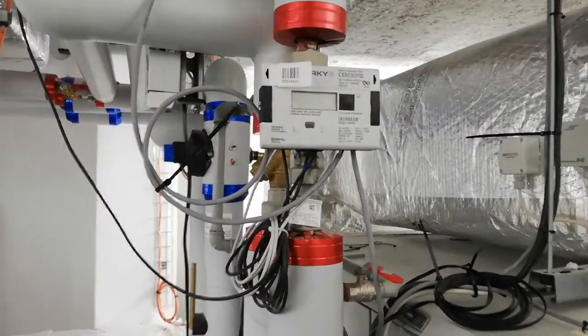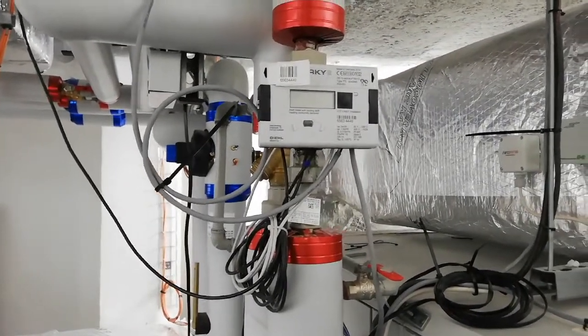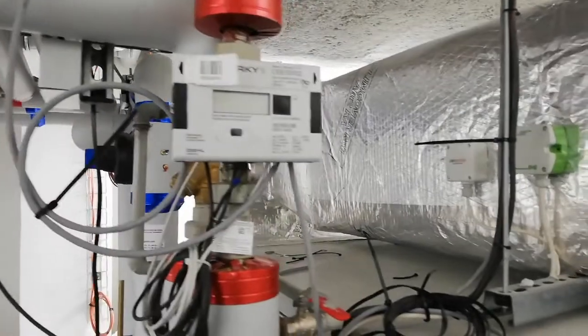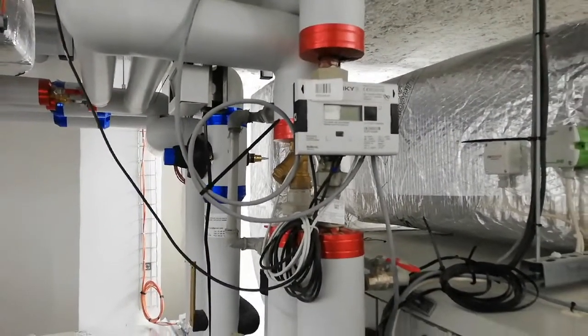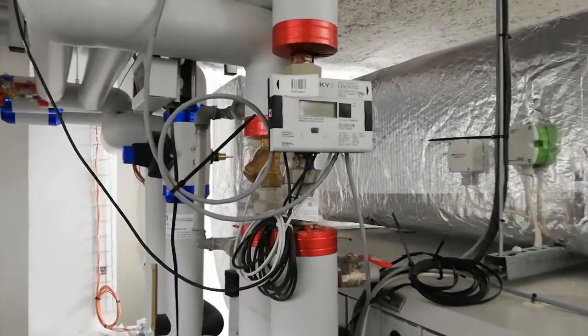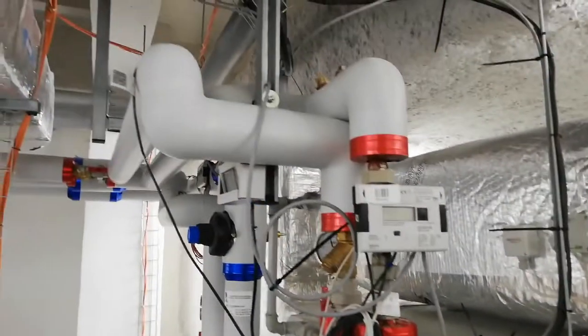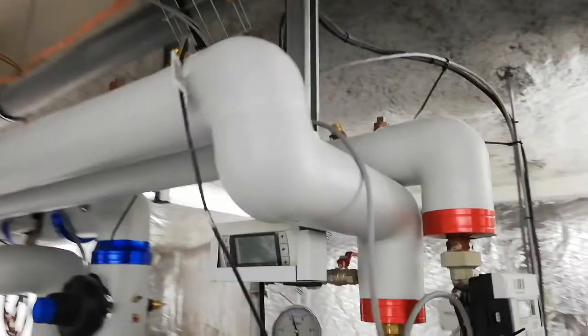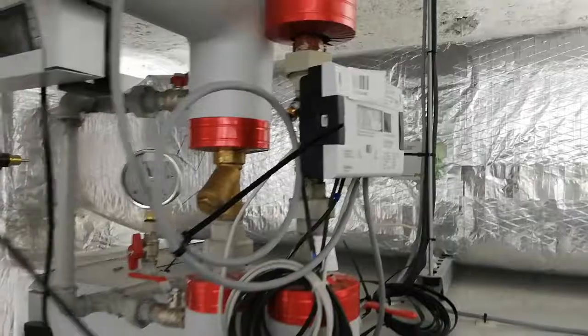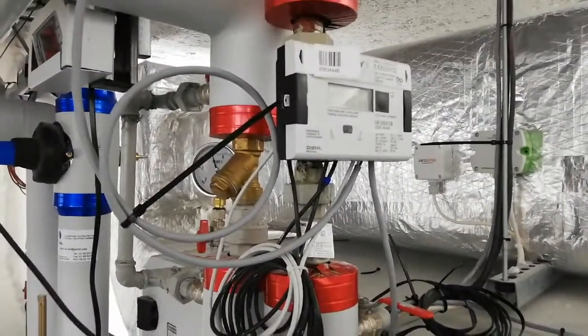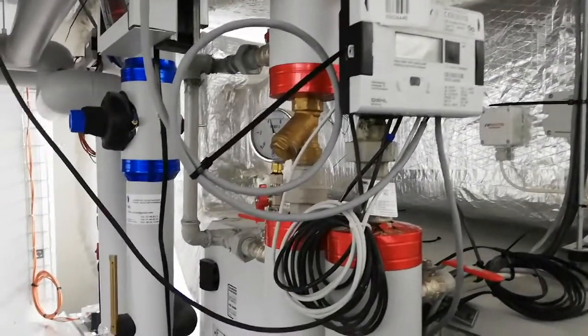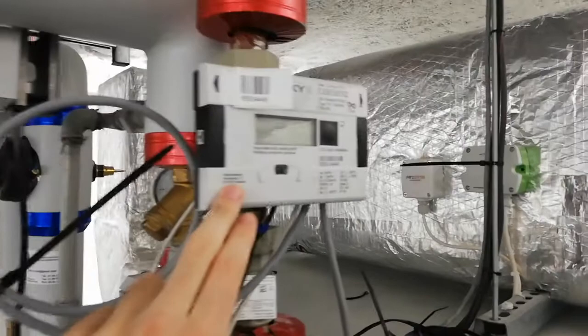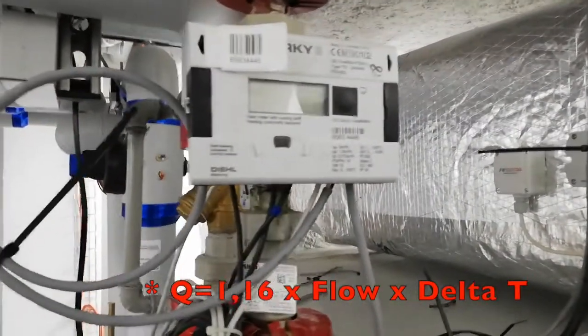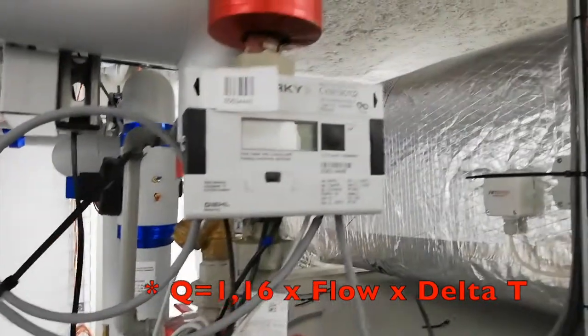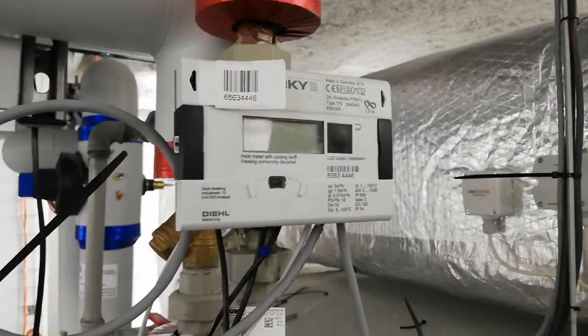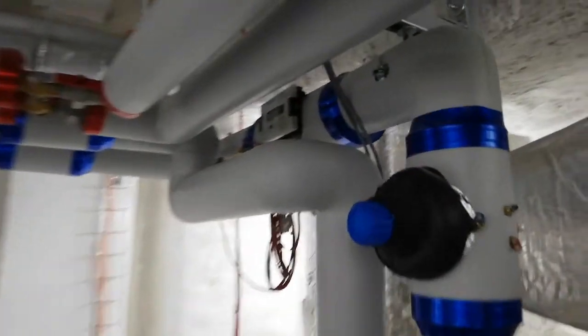Then you have the energy meter that I like to put on my units in order to measure the consumption for building purposes. The energy meter is always installed on the return. You will have to install two temperature sensors, one on the supply and one on the return. The energy meter is going to calculate the delta between the supply and the return temperature, and it's also able to measure the flow. So when you have the delta T and the flow inside the pipe, you get the energy consumption of the hot water coil. And we have the same for the chilled water.